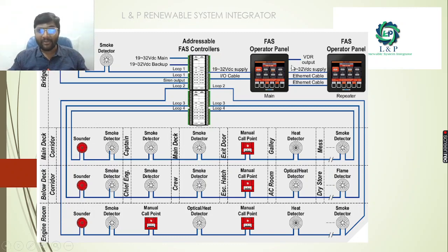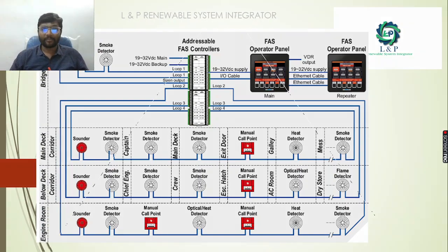As you can see, we have a main fire alarm control panel and also a repeater. It operates with a 19 to 32 volt DC supply, and we establish communications with Ethernet cables. Most importantly, through the different fire alarm controllers, different loops have been established. As you can see, we have 4 different loops. And sometimes, when covering the longest distances, we go for repeaters.